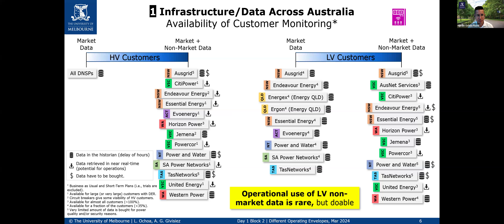In terms of customer monitoring, let's separate market and non-market data. Market data are the kilowatt-hours normally measured every 30 minutes that go to corresponding retailers. Non-market data is the active and reactive power, voltage magnitude, current magnitude, and corresponding angle between voltage and current — information that distribution companies can use to improve operations and planning. When there's a smart meter, most distribution companies have access to market data, but non-market data depends.